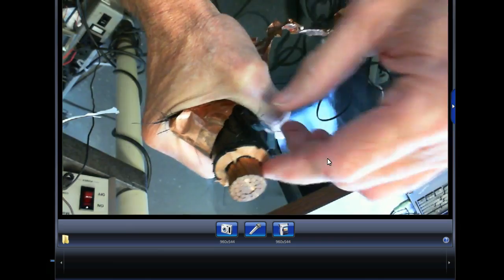And then we have the shield. What's the function of the shield? The primary function is to equally distribute the electrical stress around the insulator. If we don't do that, and there's any other metal around there, it's going to try to move the magnetic field toward that metal. So all your voltage will be held in by one side of the insulator. That makes sense? So the primary function of the shield is to equally distribute the what? Equally distribute the stress around the insulator. Plus it prevents the cable from generating a lot of electromagnetic interference too. But the primary function is so we can lay this thing across any metal and it won't cause any problems.